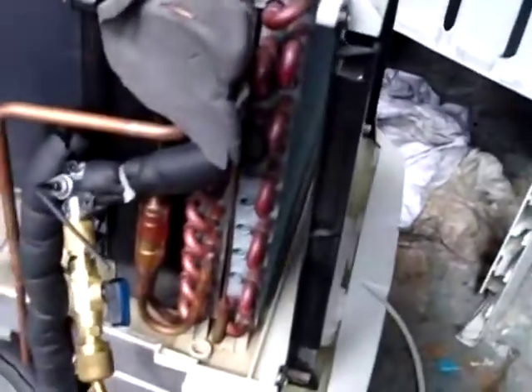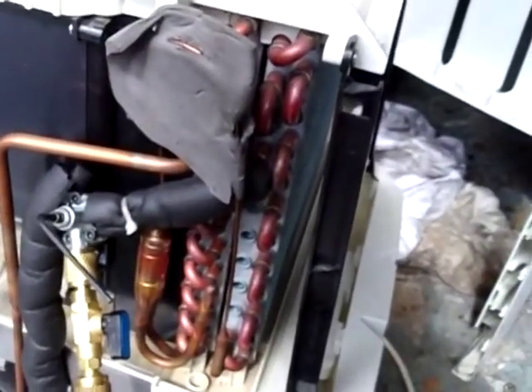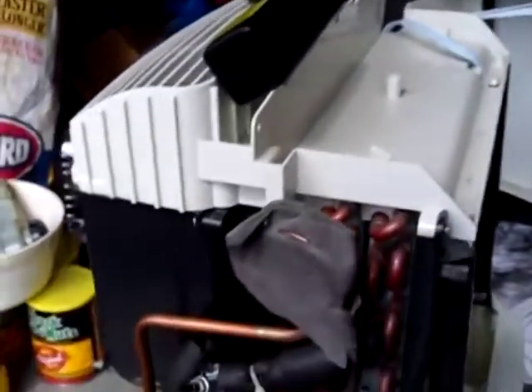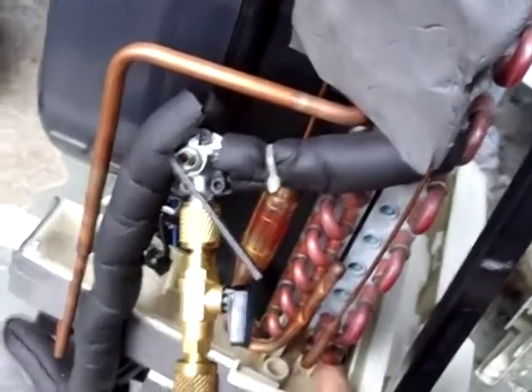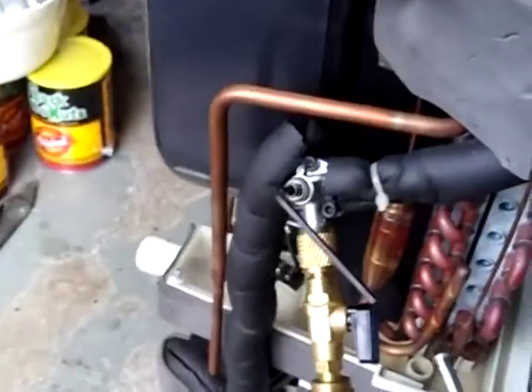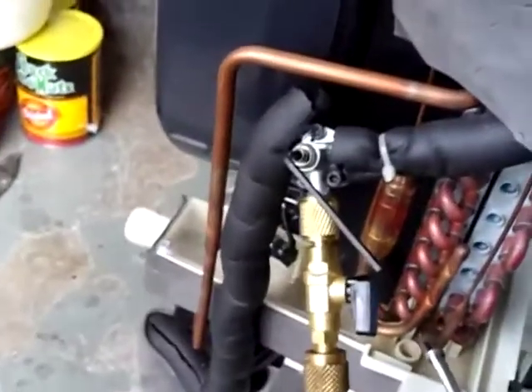So I put a little bit of pressure into it, maybe like an ounce, not even an ounce of refrigerant. And I looked around, I didn't find anything, but when you're looking and you're searching, then you start to see things. So down here I see some rust or corrosion right at the beginning of the cold coil, the evaporator. So I see the rust there, and I did put the instrument there, and I have had some activity. If I fully charge it up, I'm pretty sure it's going to be really obvious there. I'm assuming that's the thing. The leak detector did help me.